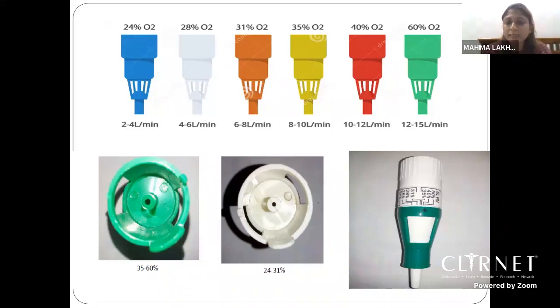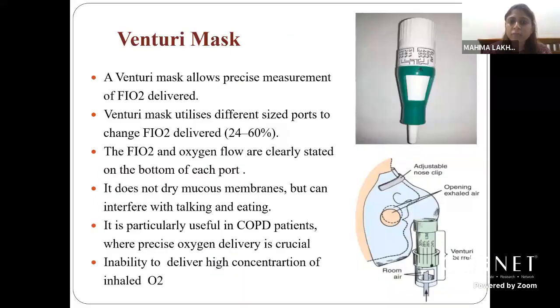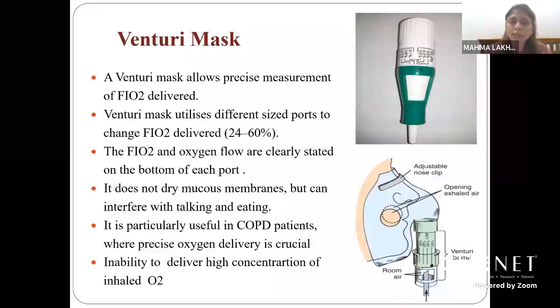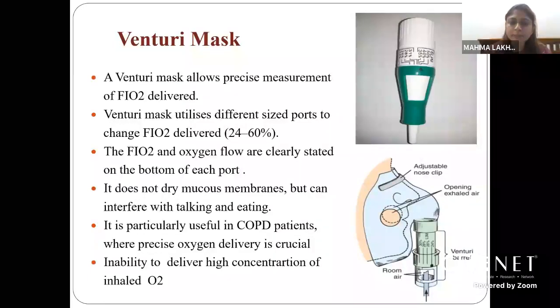Another way is that we can adjust the FiO2, and even then the entrainment ports are fixed. If we are giving a patient an FiO2 of 35%, the entrainment port will be fixed, and a fixed amount of room air will be entrained in that case. That is why it is known as the fixed performance system. So a Venturi mask will allow a precise measurement of FiO2. It utilizes different size ports to change the FiO2. A maximum of 60% can be given. The FiO2 and oxygen flow are clearly stated on the bottom of each port.